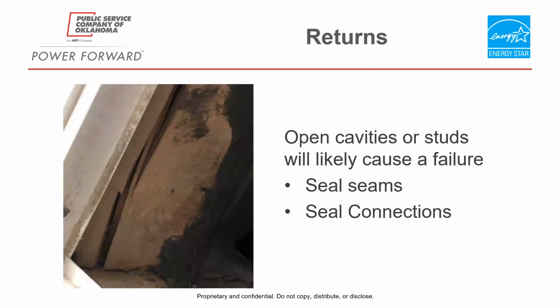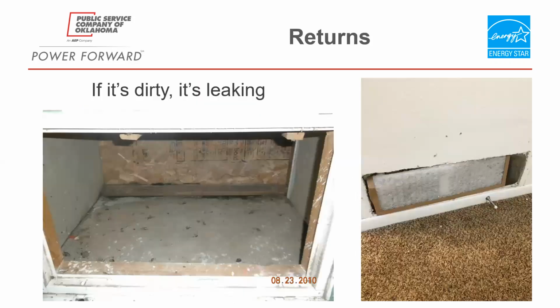This is a return, and as you can see, anytime you have two pieces of material coming together, you could potentially have a problem with air leakage. This is a good example of it here, and down here's another good example. You can actually see where dirt has accumulated right there — that shows me there's air leakage coming through those areas. So we need to make sure all that's sealed up with mastic, and everybody will be happy and it'll work great.